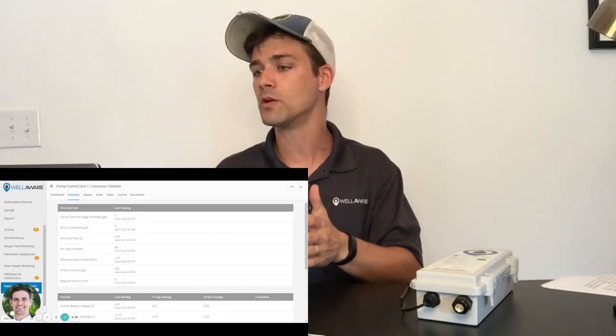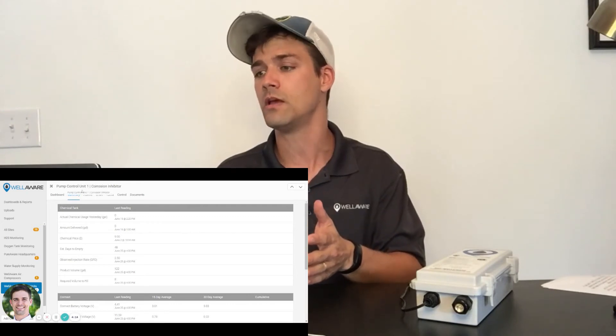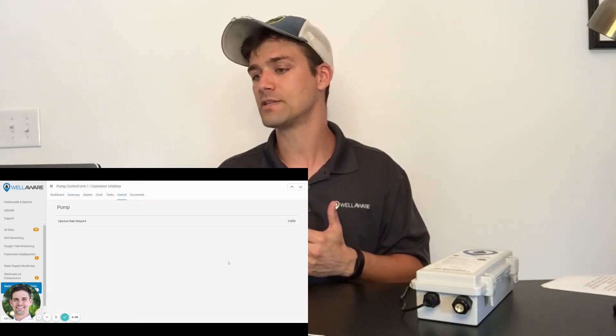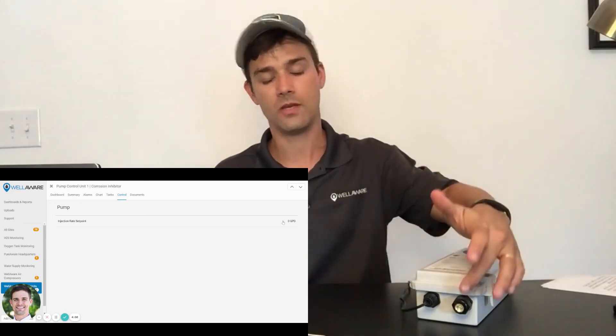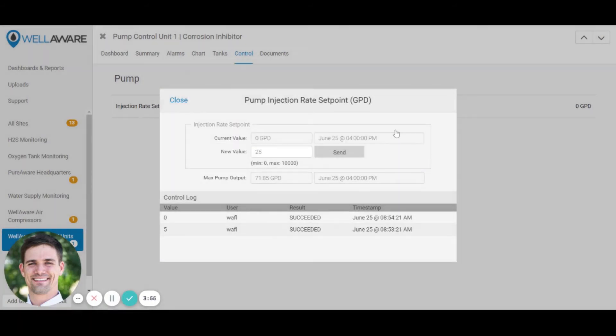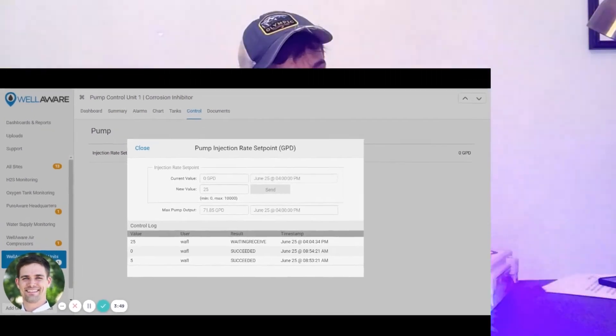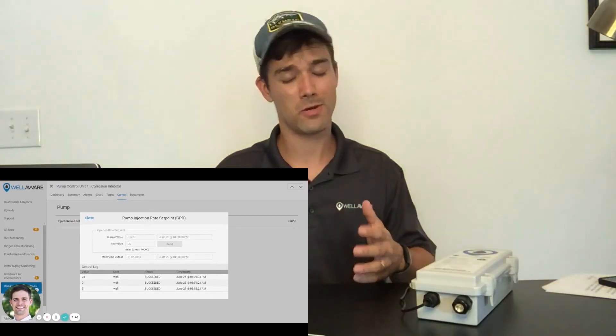In the web app, I'm looking at a summary view for a chemical injection pump controlling corrosion inhibitor injection. Going to the control tab, I can see the injection rate set point — the pump is currently off and the LED is off. I click 'injection rate set point,' set it to 25 gallons per day, click Send and Submit. An audit log shows the set point change, and looking at the Connect, it's now controlling that pump at about 50% duty cycle — exactly what we want.